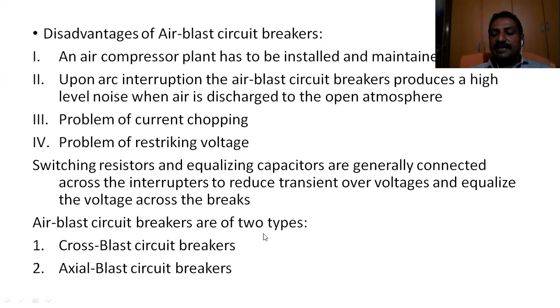Then, based on how the air is pumped in between the two contacts, air blast circuit breakers are classified into two types. Number one is the cross blast circuit breaker, and number two is the axial blast circuit breaker. First, I'll go through the cross blast circuit breakers. In this circuit breaker, which contains two contacts, a fixed contact and a moving contact, when the moving contact moves away from the fixed contact during the fault, an arc is immediately developed. To extinguish this arc, high pressure air is directed perpendicular to the arc for its interruption. So that is the classification of the cross blast circuit breaker.